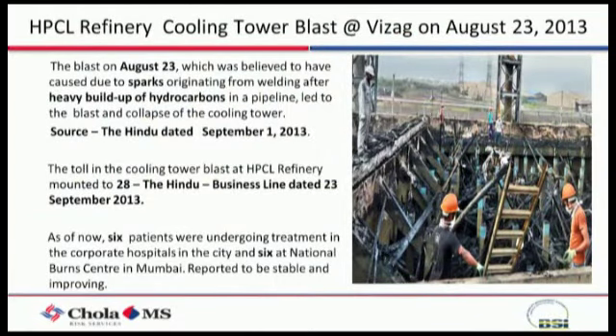These are some of the accidents which have taken place in industries. There had always been reasons because of non-compliance to hazardous area classification. In this case, it was a refinery cooling tower where people did not expect vapours to accumulate. Arc welding was ongoing, which generated a spark, and the vapours present in that area engulfed and created a major fire. It was widely published across many newspapers.